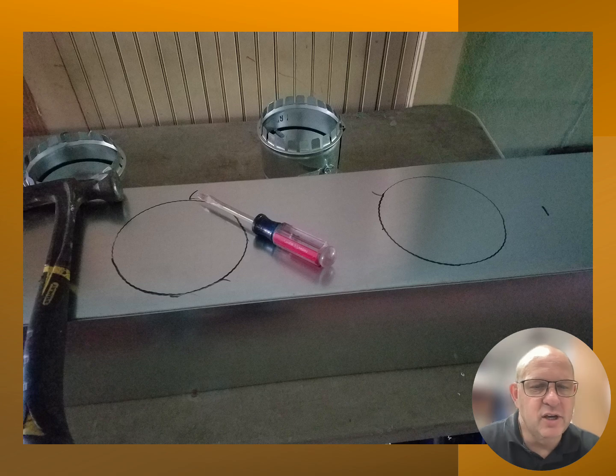Continuing on our process, we can see that we have drawn a circle around the actual ductwork to show us exactly where these takeoffs are going to go. A couple of rules that you need to understand about the takeoffs. The takeoffs should not be at the end of the trunk. If the takeoffs are at the end of the trunk, we will lose the pressurization of that trunk to be able to push air out evenly through all the distribution branches that are on this main trunk. So we want to come back at least a foot, 12 inches, off the end of the pipe, so that we can pressurize it and get good static pressure, good velocity, and good total pressure within our ductwork, and that air will flow out evenly through all the different branch runs that are a part of it.